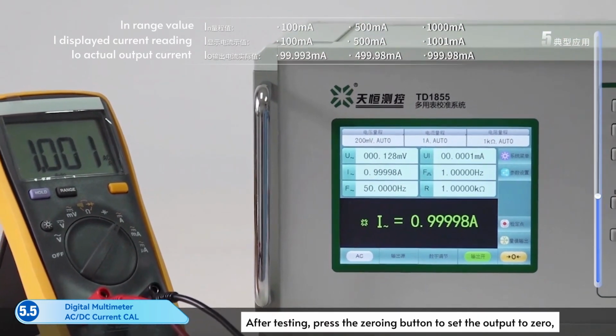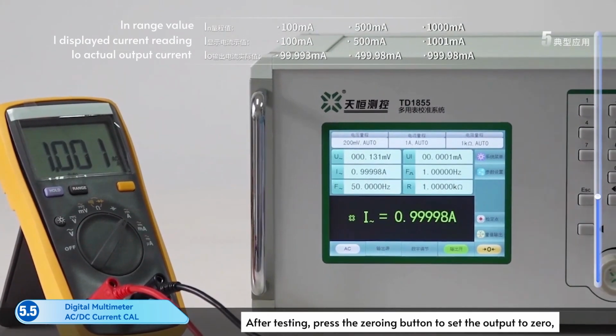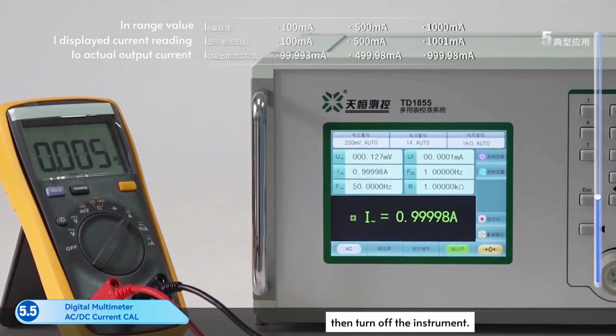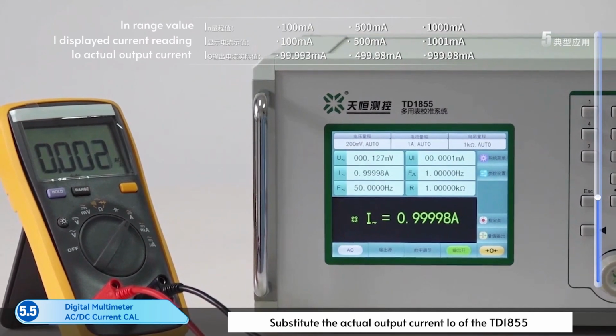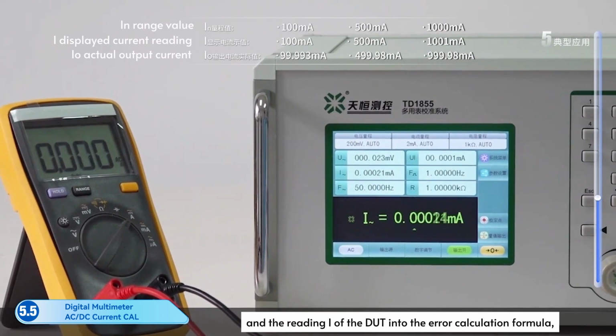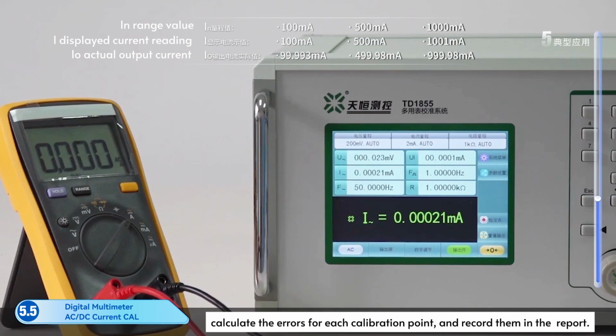After testing, press the zeroing button to set the output to 0, then turn it off. Substitute the actual output current and the reading of the DUT into the error calculation formula. Calculate the errors for each calibration point and record them in the report.